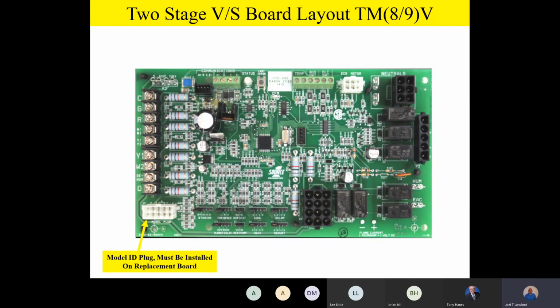And what it is, it configures the board. It's a model ID plug. It configures the board for the size of the furnace it's hooked to. So it's important that if you have a replacement board, be sure to take the model ID plug off the old board and snap it onto the new board. Then the first time you power that board up, it'll know it's on a particular size furnace. So from an inventory standpoint, this is really kind of cool, because now you don't have to have 57 different boards on your truck for these furnaces. Basically, that model ID plug tells the board what furnace it's hooked up to.